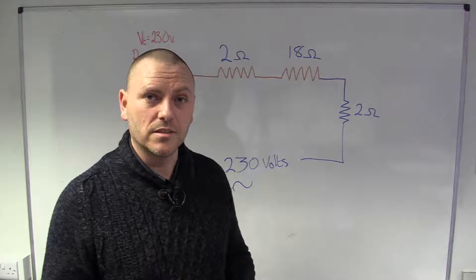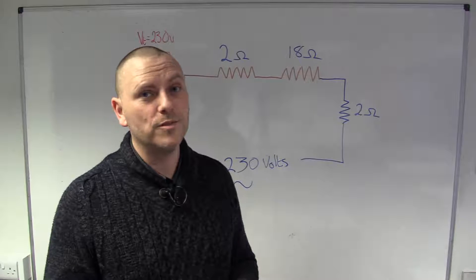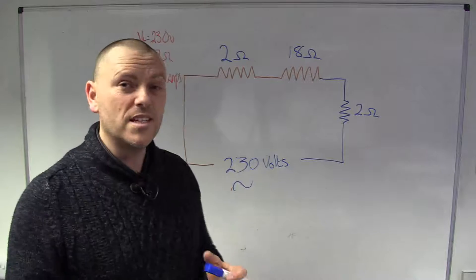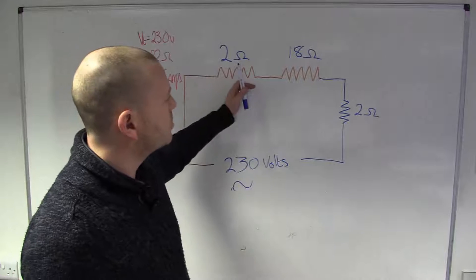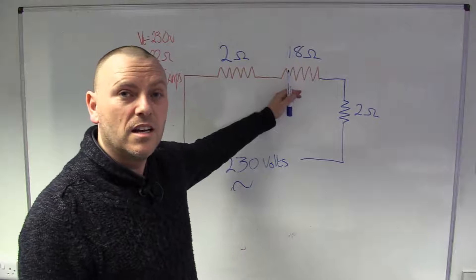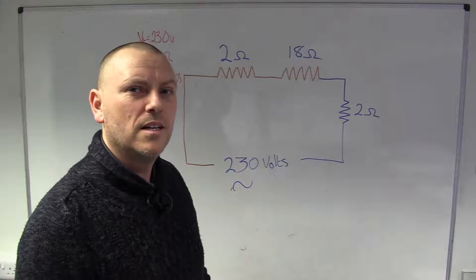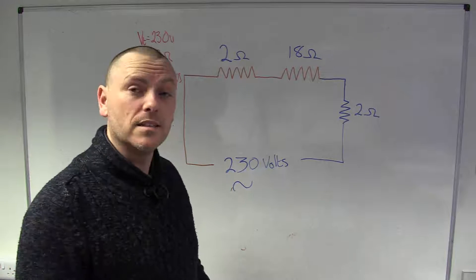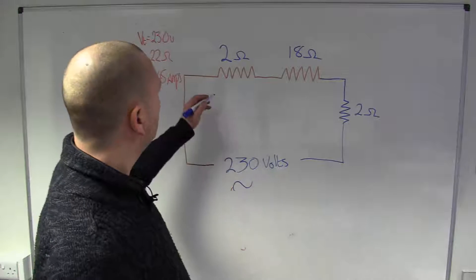That's quite a problem with inductive loads, because they'll pull more current to make up the loss of power, which can overheat our cables, our switch gear, and can be quite dangerous. With a resistive load like this, if our first cables had so much resistance that it wasn't getting enough energy, it wouldn't be the end of the world. It just wouldn't get as hot as we'd expect. Resistive loads, a little bit safer with the volt drop, but inductive loads is something to consider.